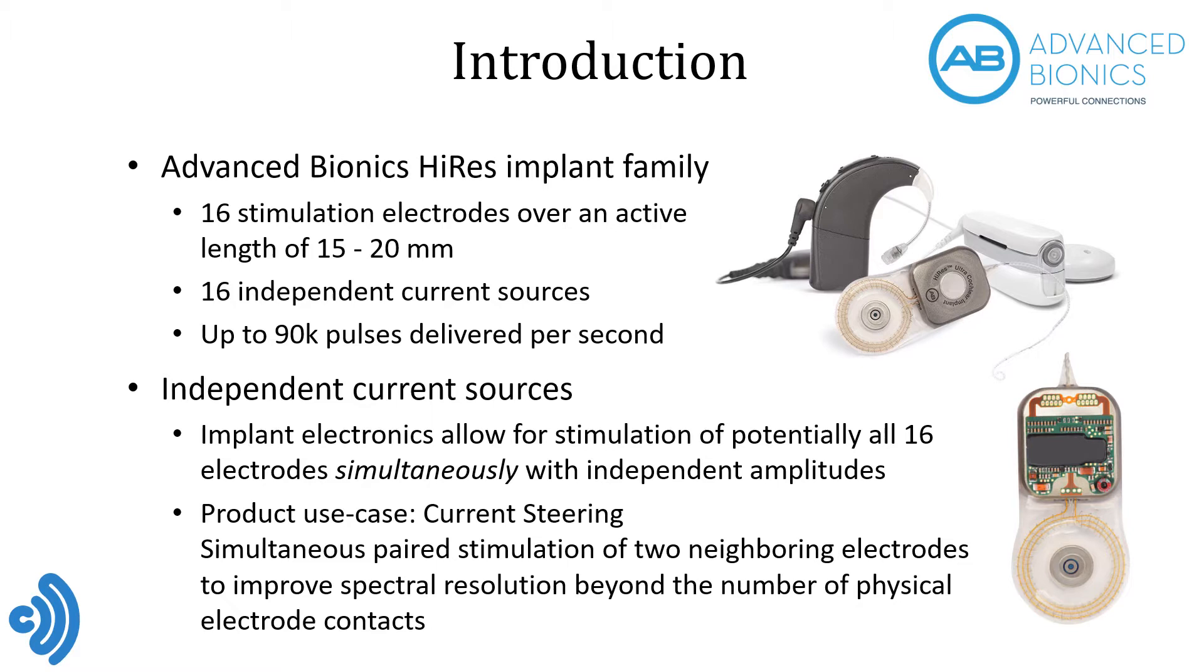In our commercial speech processors, we use some of this capability to achieve an effect called current steering. In current steering, we stimulate neighboring pairs of electrodes simultaneously in order to increase the number of different pitches a CI user can hear beyond the number of physical electrode contacts in the array. So next, I'll explain to you the concept of current steering. And I'll show you how, in general terms, we combine current steering with the principle of continuous interleaved sampling. Then we will take a detailed look at the signal processing steps of the spec res strategy specifically, step by step, so that afterwards you should be very well equipped indeed to dive into the source code yourself and find your way around easily.